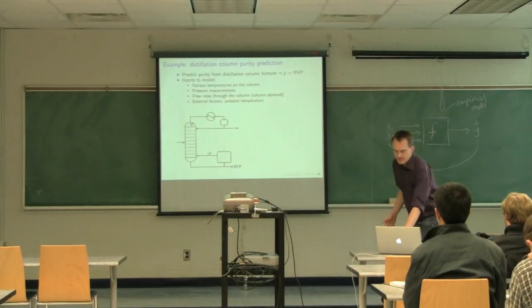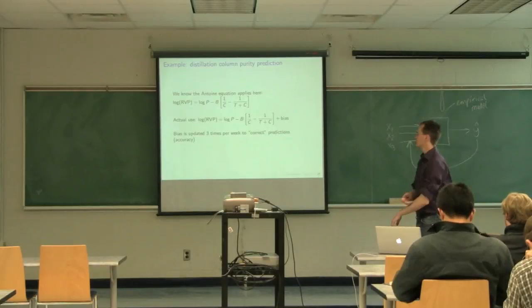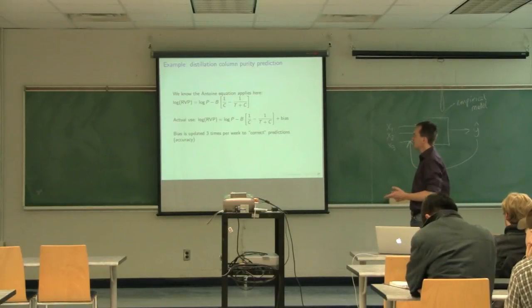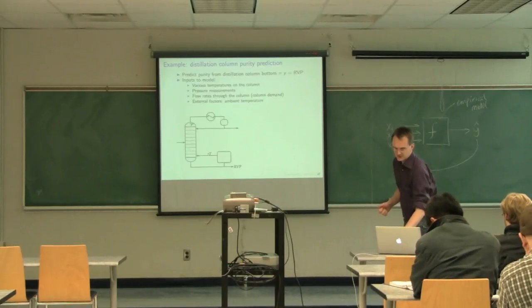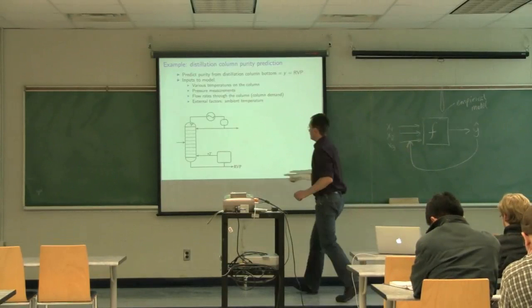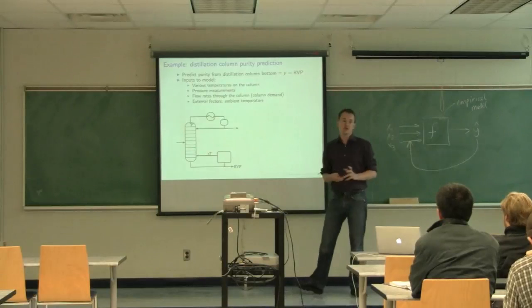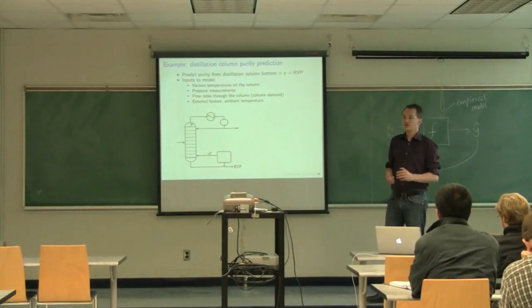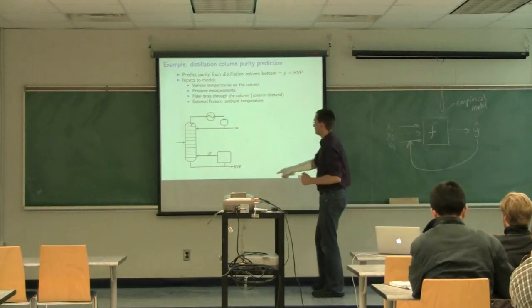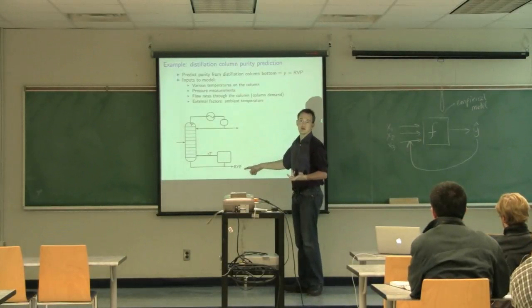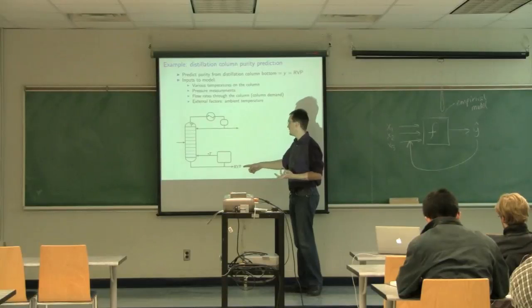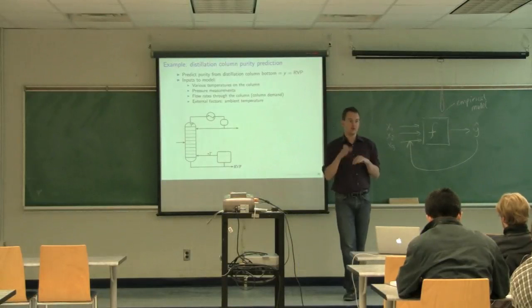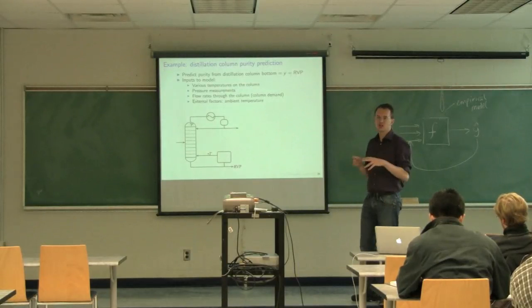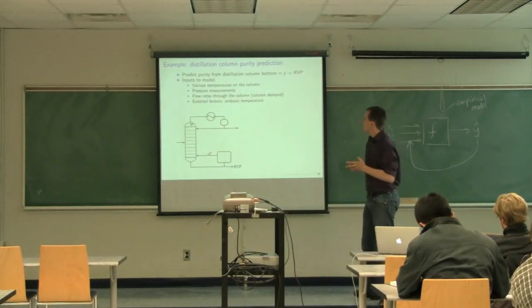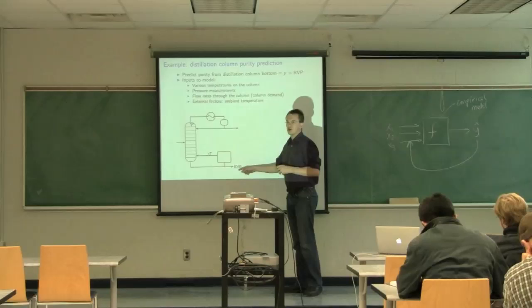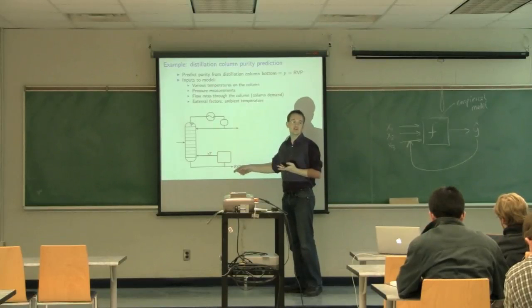Now, just some background: what this company was doing is using this vapor pressure value down here as their critical control variable. This product coming out the bottom is what they were selling to their customers, and they needed to keep that vapor pressure on target within a certain range. That target changed depending on the time of year. But that is their control variable, and they in fact had that under feedback control.